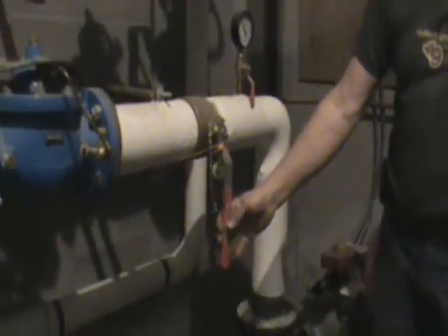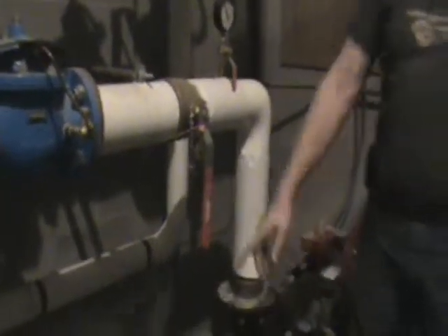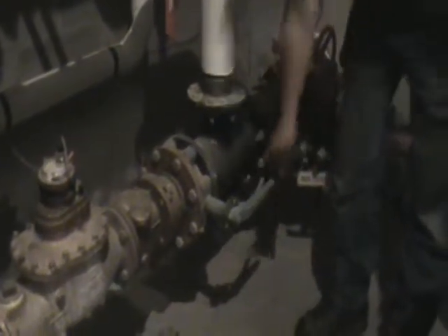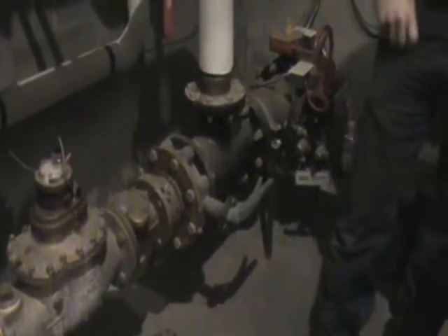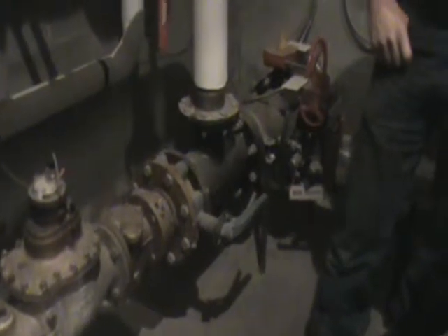This one here is the bypass, which should be kept closed at all times. Which one would you turn off if you had to? I'd turn this one here off, the fastest one to turn off. It's the big gray one, the main one down the bottom here. With these types of valves, when they cross the pipe, they're shut off, and when they run with the pipe, they're on.